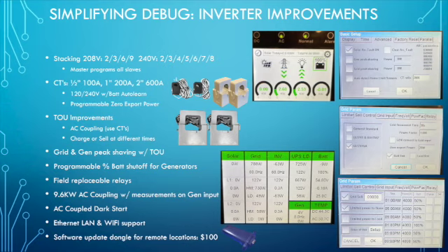Another nice thing is the master programs all the slaves. You don't have to do anything but the master programming. Also, since we did more installations out in the countryside where they use aluminum wire, we introduced larger CTs, and then with big parallel systems, we introduced these ginormous 2-inch 600 amp CTs that fit around your wrist. A couple things to note: if you want to auto learn the CTs, so you can't miswire the CTs in different directions and all kinds of other things, it only works if you're 120/240, and it only works if you have batteries connected to the grid.